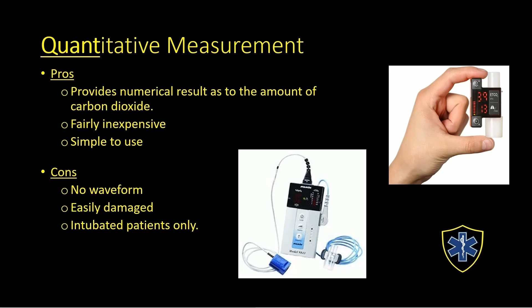Now, the most advanced version of it is what we call quantitative with a waveform. Now, this provides us not only the numerical result that we see here, the 41, as far as what the carbon dioxide level is, but it can also be used many times in breathing patients. And this waveform can be an excellent assessment tool in our assessment. Now, these are easily recorded, they're documented, and it's very easy for us to monitor. Now, these are definitely the most expensive of all the options. Many times they're going to require calibration, and some versions can be damaged pretty easily.